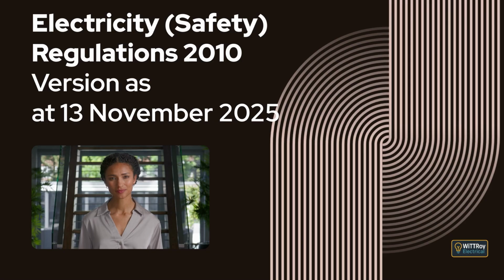We'll now cover rules for low and extra low voltage installations. Reg 59 Low and extra low voltage installations to comply with AS/NZS 3000. This regulation explains that every low or extra low voltage domestic installation, or part of a domestic installation, must be installed, tested, inspected, and connected to comply with Part 2 of AS/NZS 3000 if it has a maximum demand at or below 80 amperes per phase for single phase, or 50 amperes per phase for multi-phase.